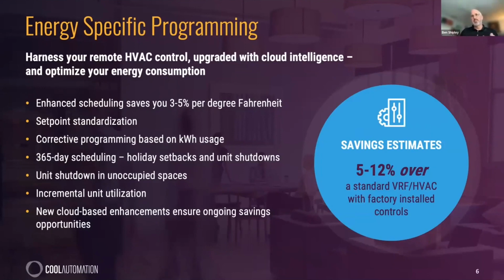Probably the first and most straightforward one is enhanced scheduling. A rule of thumb in the HVAC industry is that any opportunity to trim back your set points by a degree represents a 3 to 5% reduction in the energy use of that mechanical unit.